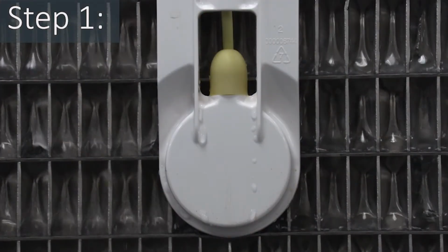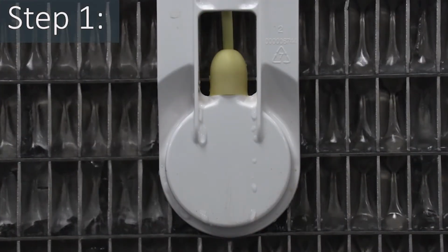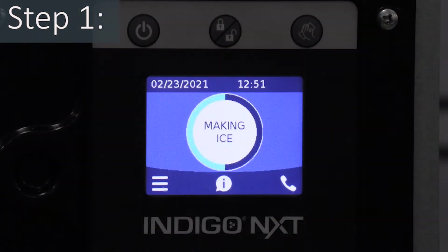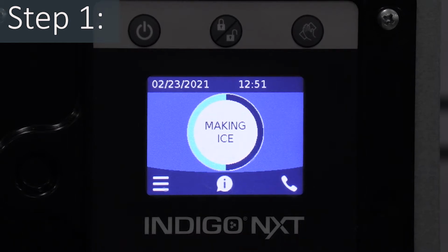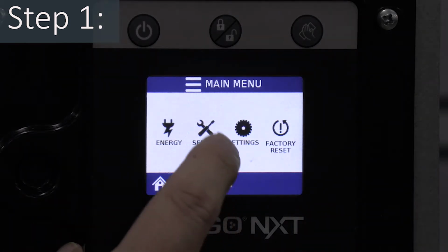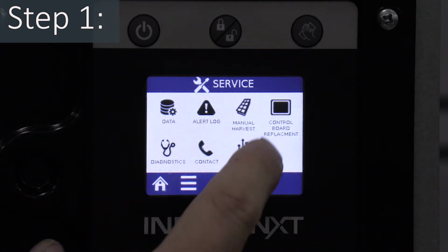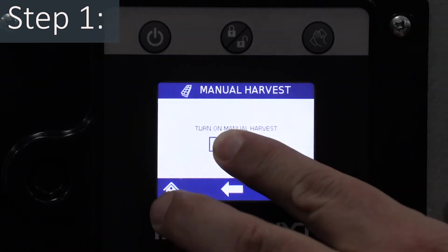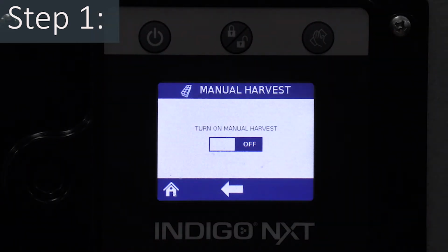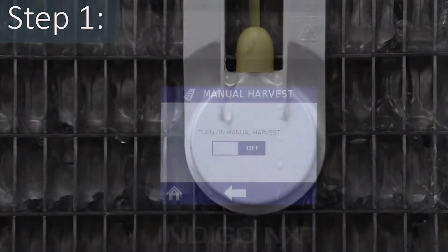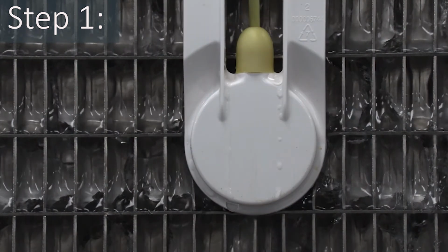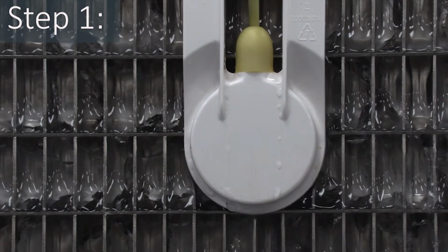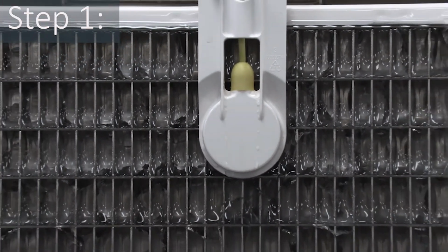Step 1. Remove all the ice from the evaporator when present by turning the ice machine off and allowing it to melt. You may choose to initiate a manual harvest through the display by pressing Menu, Service, Manual Harvest, and then press Turn on Manual Harvest while the ice machine is on and in ice mode. Do not attempt to chisel or force ice off the evaporator. Damage may occur.